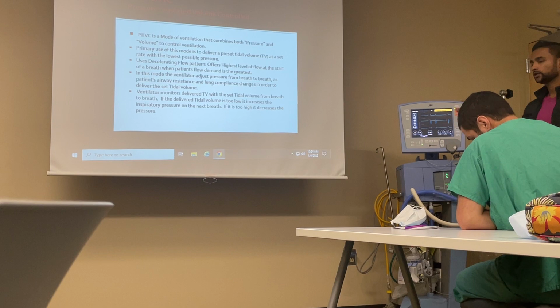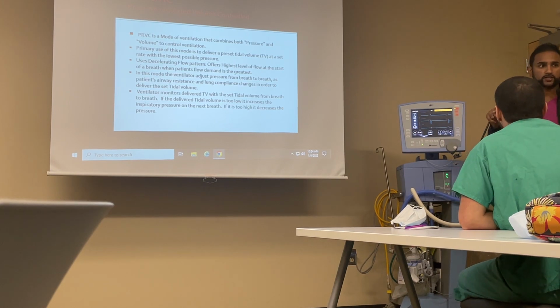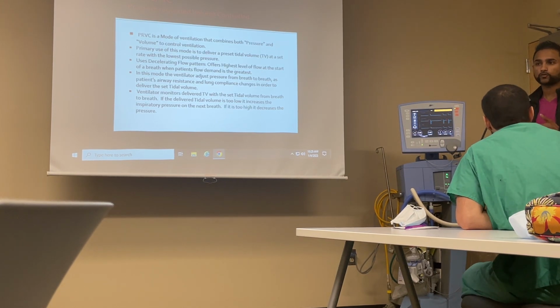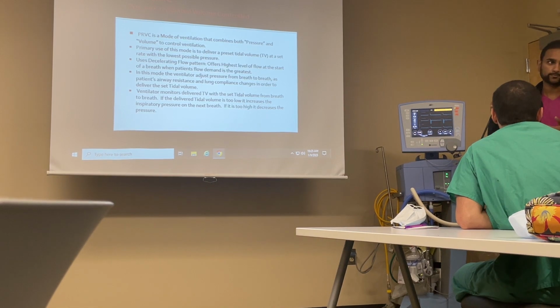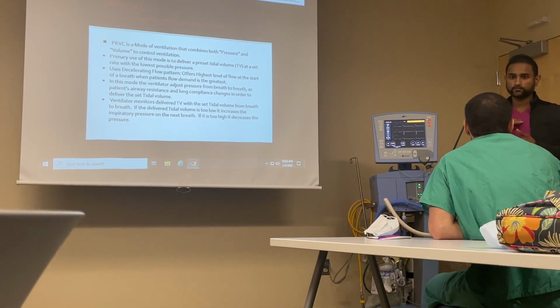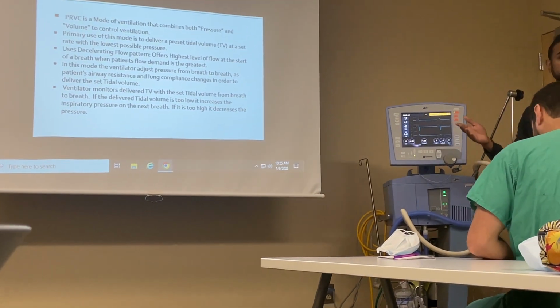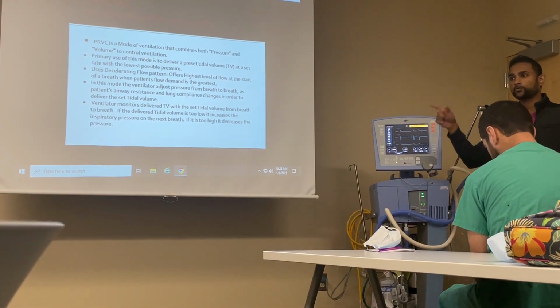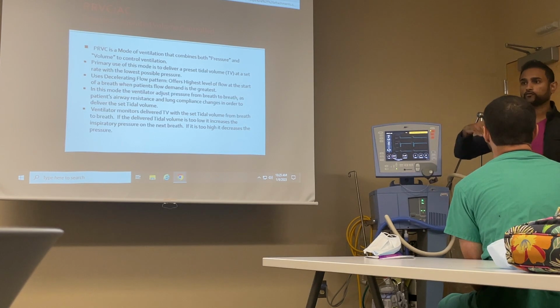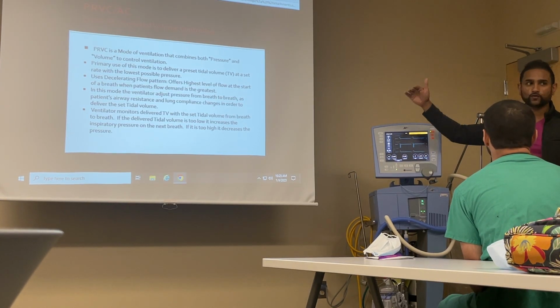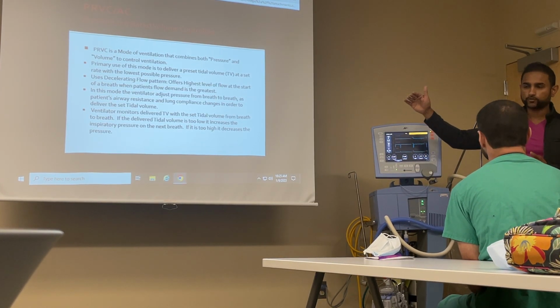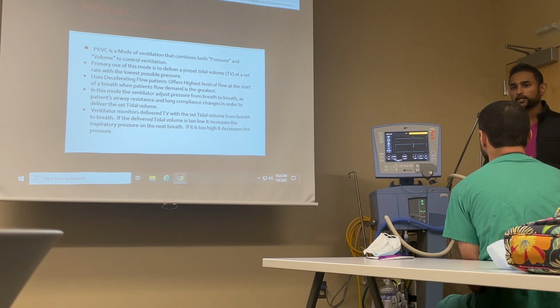Okay, in the next cycle of breath, which is the next 5 seconds, instead of 300, I'm going to give 350 and assess the internal pressure. Oh, okay, peak pressure is still reading less than 40. I like that. Third breath, it's going to ramp it up to 400. Fourth breath, 450. Eventually, it's going to reach the target volume of 500.